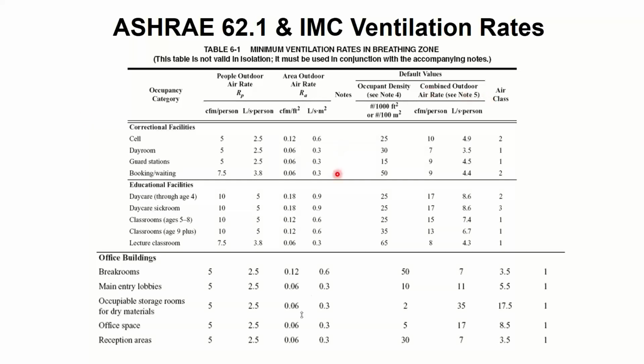All right, last question, and then I'm going to move on, and I'll come back to your other questions later. Does a VFD on a supply fan affect the minimum outdoor air requirement? No, it doesn't affect the outdoor air requirements, but to your point, it does affect the actual outdoor air.